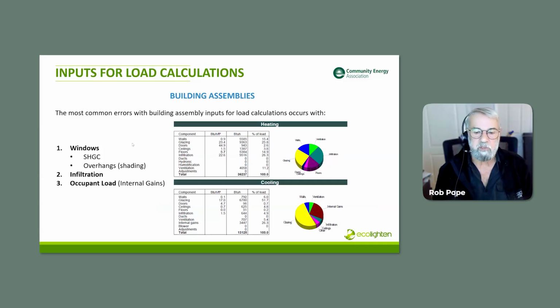So this is an example. The most common errors when it comes to windows are solar heat gain coefficient and overhangs. We'll talk about that in a bit. The other thing is infiltration - it's surprising how often that's inaccurate. And occupant load.